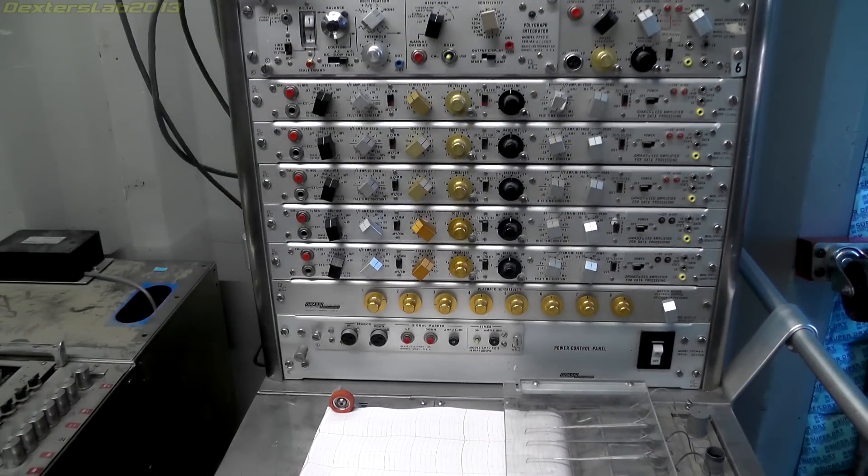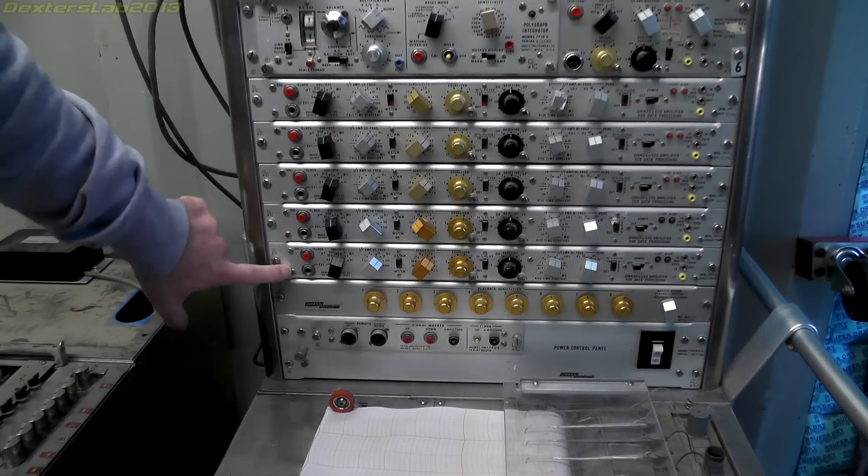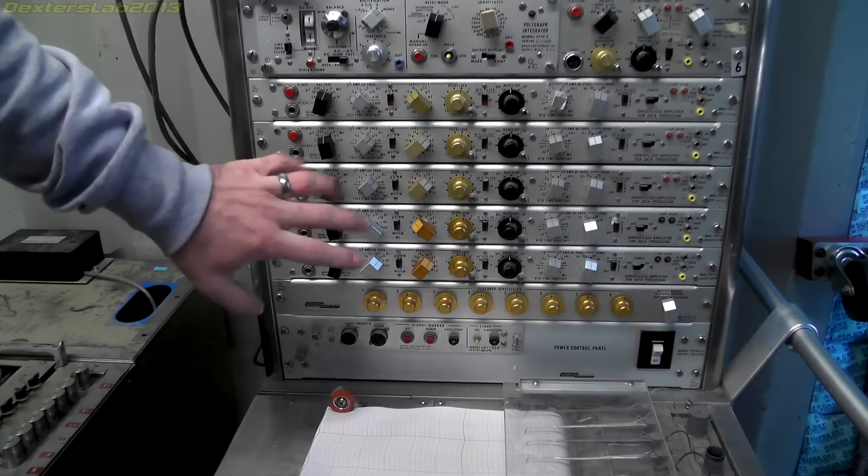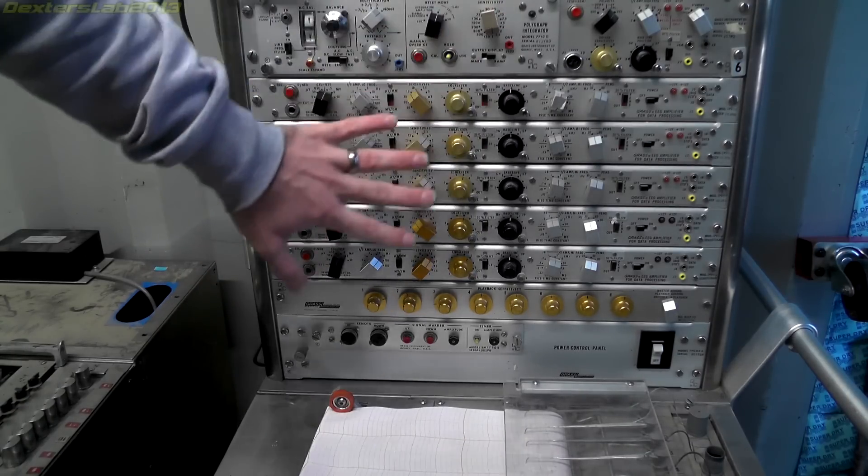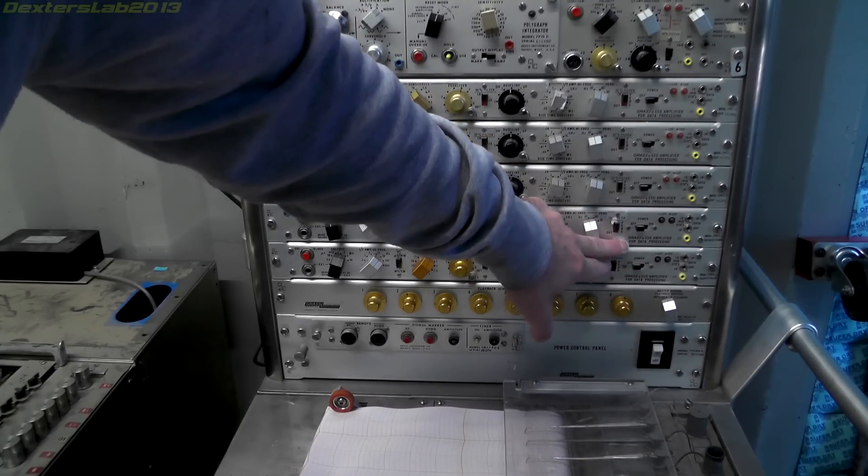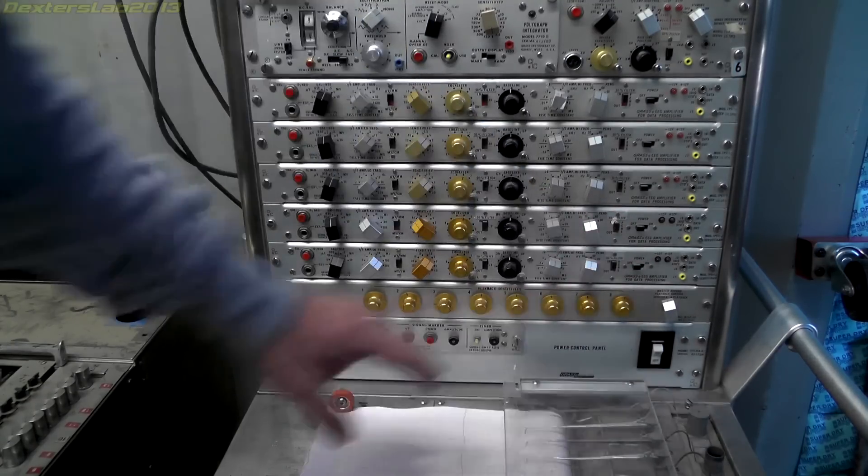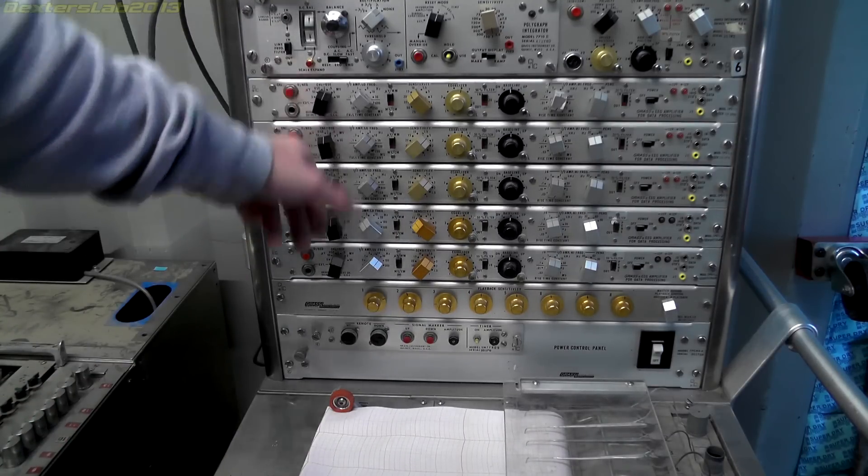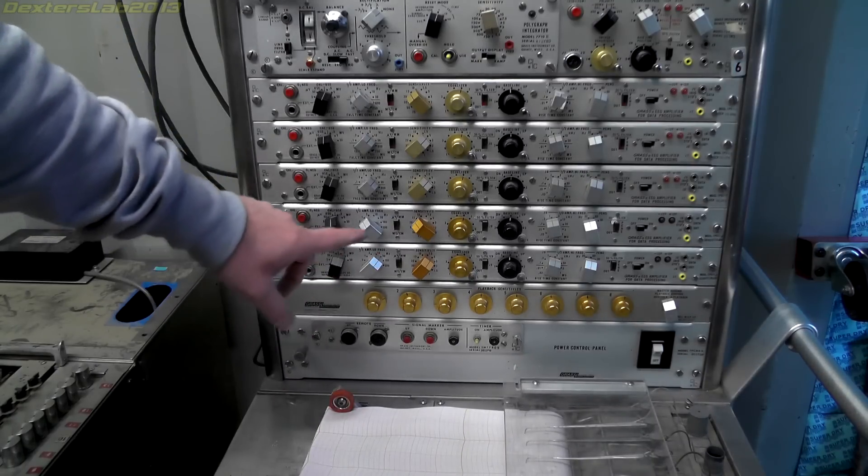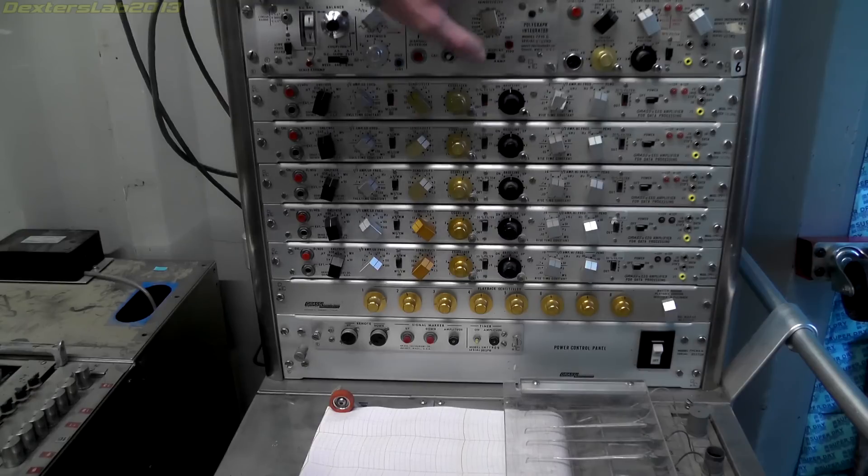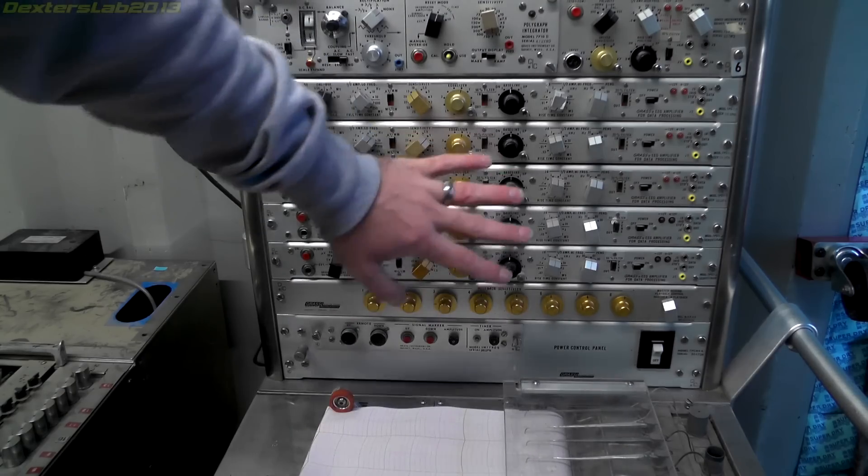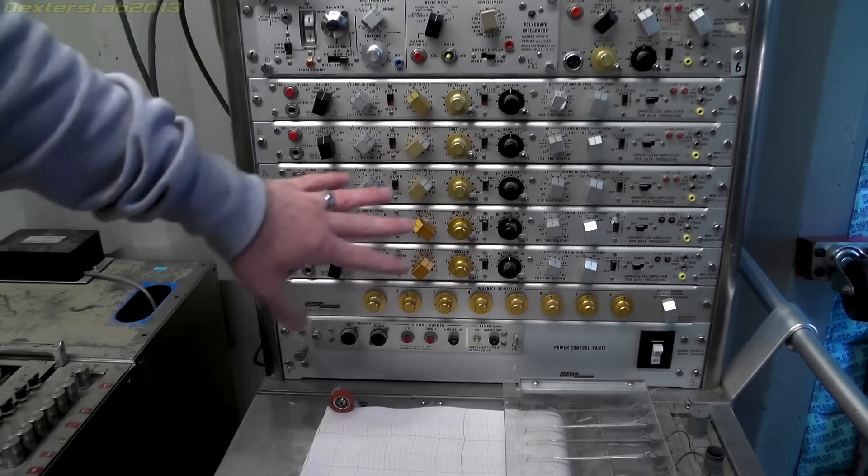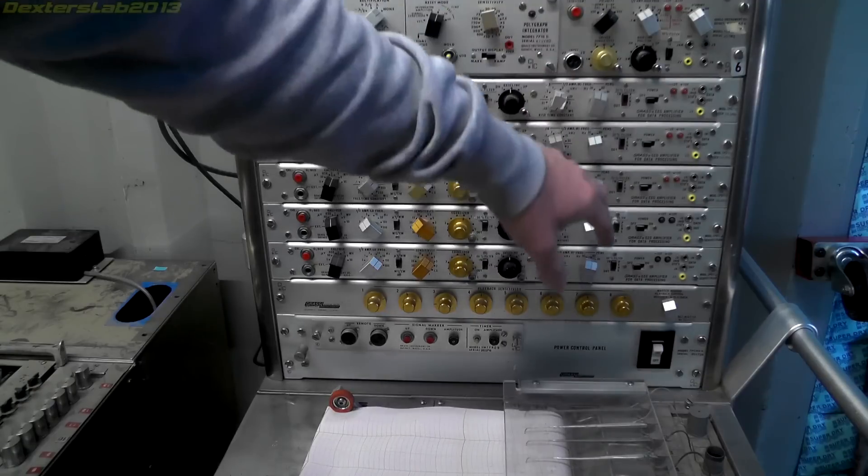And a bit further down we have these modules here. There's five of them. Why that doesn't match up to the number of amplifiers I don't know. But these are titled EEG amplifier for data processing. Now interestingly these are only attached to the power supply in the back. There's no signal transport between the amplifiers and the preamps into these. So I think these are expected to be patched in using cables on the front here. We have various data in, out and other little connections here. There's an external connection there. So I think these would be plugged into the driver amps with little patch cables which I don't have.